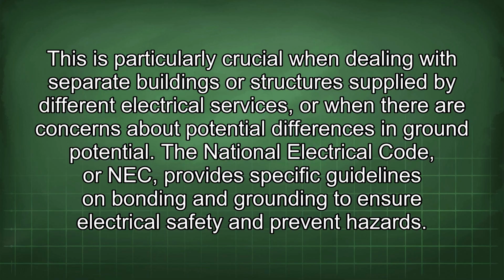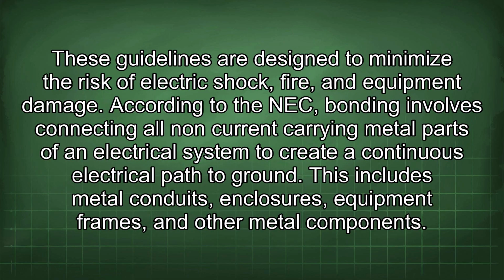The National Electrical Code, or NEC, provides specific guidelines on bonding and grounding to ensure electrical safety and prevent hazards. These guidelines are designed to minimize the risk of electric shock, fire, and equipment damage. According to the NEC, bonding involves connecting all non-current carrying metal parts of an electrical system to create a continuous electrical path to ground. This includes metal conduits, enclosures, equipment frames, and other metal components.